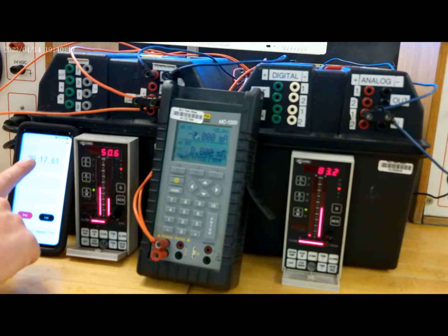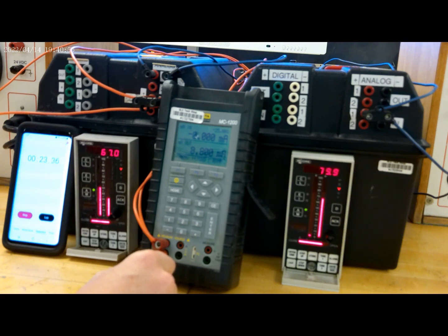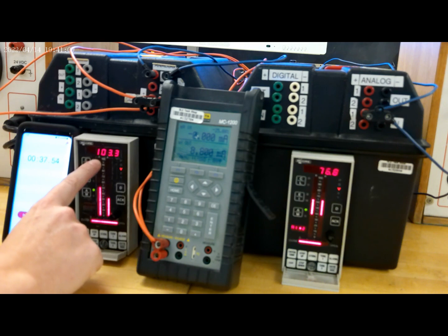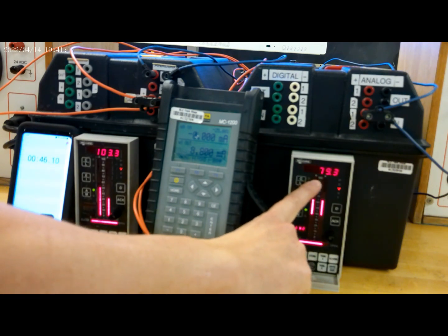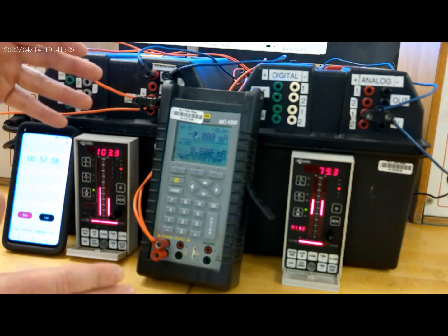Now we're watching it. We're at almost 20 seconds, and we're down to 82. We're going to see it get down to very close to 71. We're at 77, and we're at 30 seconds now. I do believe it goes to about 36 seconds. Now we've hit our maximum output, and you see it drop down to 73, which is very close. And now it's back up to 79.3, extremely close to 80. So you see that? We not only proved the math, but we proved it in reality. We proved it right here.